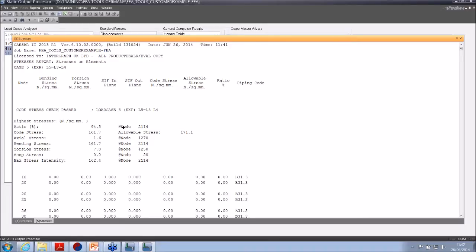It's 94%. Because we've got that added flexibility that we didn't have included in the model before, but of course it was always there because the intersections are inherently flexible. They're not rigid connections or rigid components like the Appendix D tells us to specify. So the more applicable data gave us the flexibility, and now we are no longer overstressed, even though in some cases we do have higher SIFs.